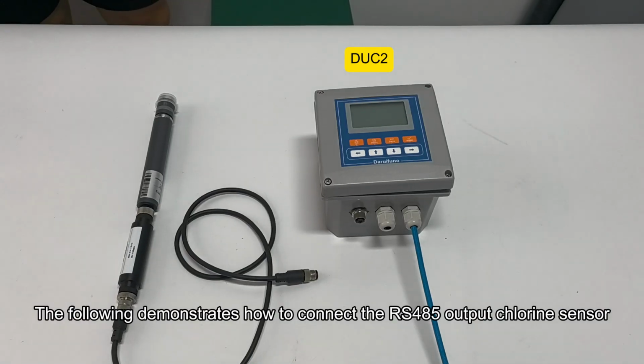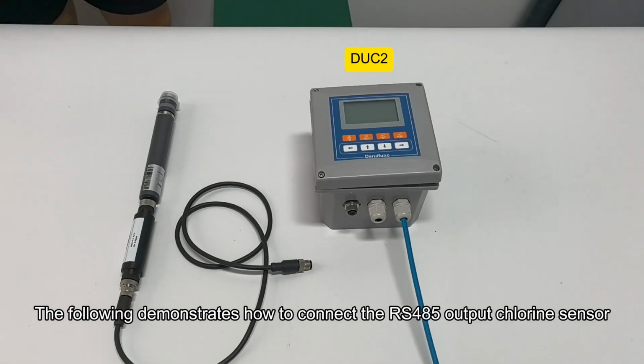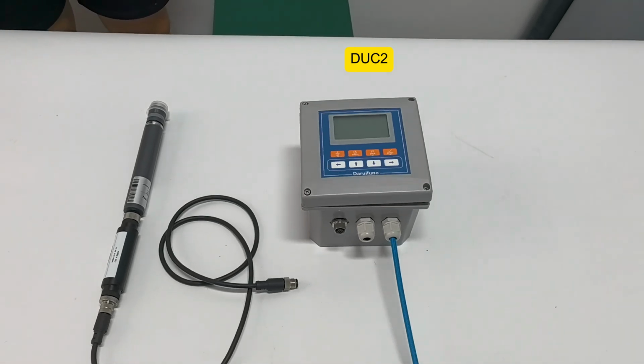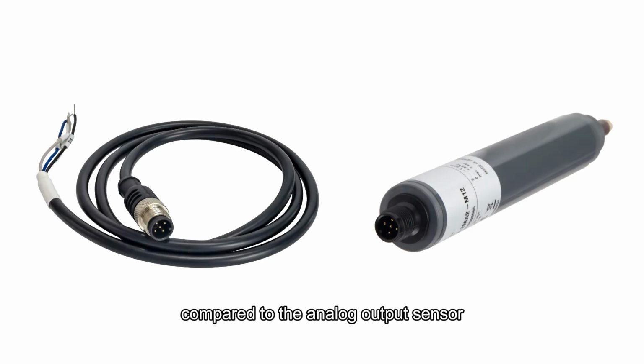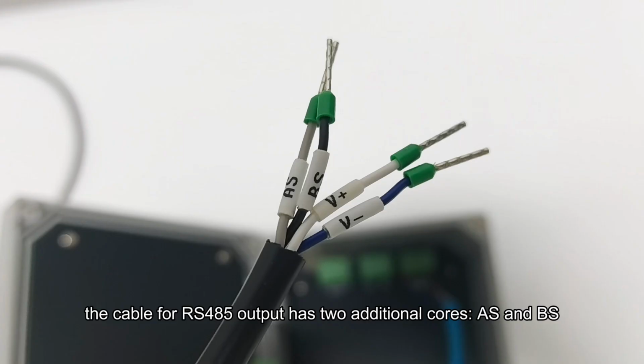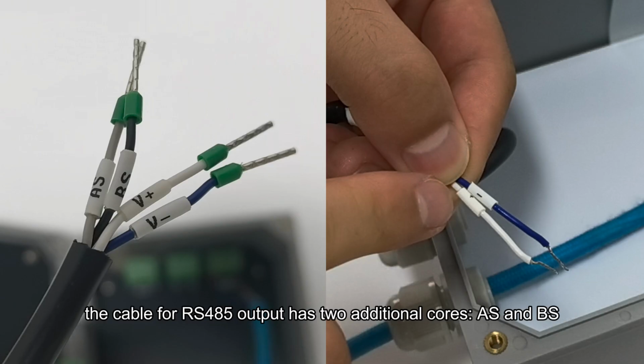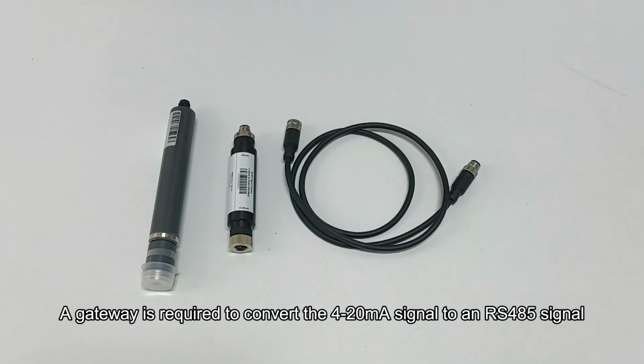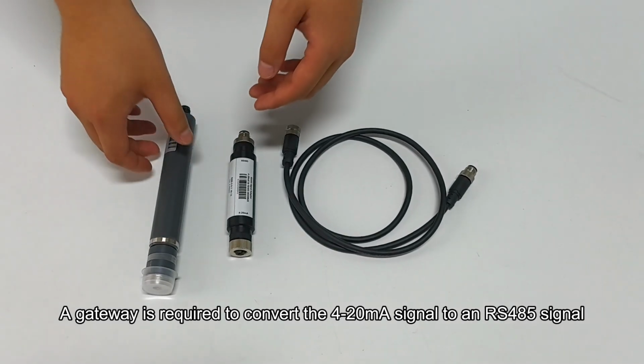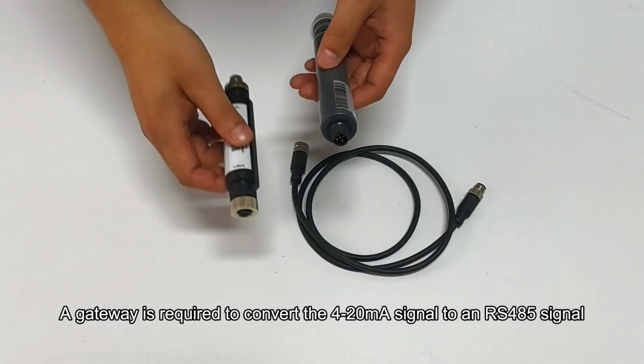The following demonstrates how to connect the RS485 output chlorine sensor with the DUC2 model digital controller. Compared to the analog output sensor, the cable for RS485 output has 2 additional cores, AS and BS. A gateway is required to convert the 4 to 20 mA signal to an RS485 signal.